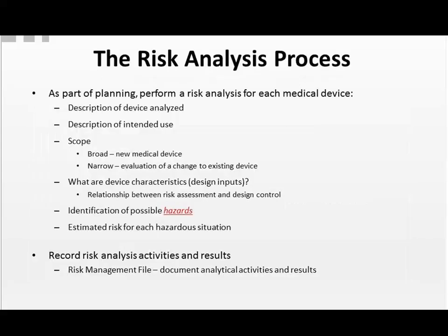Now, as you saw partly in the previous slide graphic, during the risk analysis you really must describe the device being analyzed. You need to describe its intended purpose. You need to determine the scope of the analysis. Is it broad, as would be required for a totally brand new device, or is it narrow, as would be required if we're making a design change to an existing device?